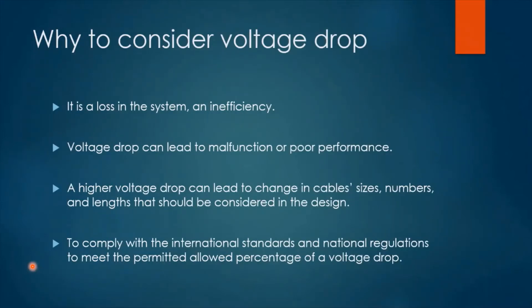Why should we consider calculating the voltage drop level? First, it represents a loss in the system and is considered an inefficiency. Second, voltage drop can lead to malfunction or poor performance. Third, a higher voltage drop can lead to changes in cable sizes, numbers, and lengths that should be considered in the design. Finally, to comply with international standards and national regulations, we must meet the permitted allowed percentage of voltage drop.